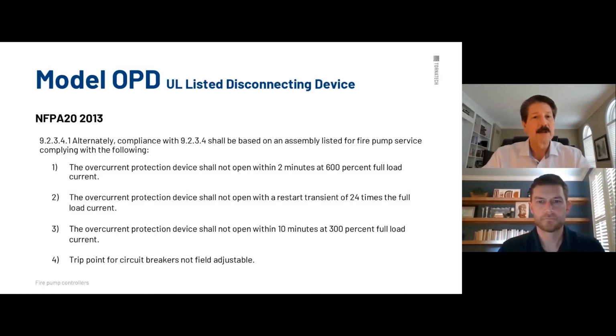Again, alternatively, compliance with 9.2.3.4 shall be based on an assembly listed for fire pump service. Comply with the following. This is key. Overcurrent protective device shall not open within 2 minutes at 600%. That's 120 seconds. The reason why is you don't want that to open before a locked rotor situation that the fire pump controller itself may see. And again, remember, fire pump controllers have lock rotor protection across the board. It's required. Locked rotor is 6 times full load amperage. And if the fire pump controller senses that between 8 to 20 seconds, it will trip the controller offline. This is a requirement. Again, 2 minutes. It's 120 seconds at 600%.